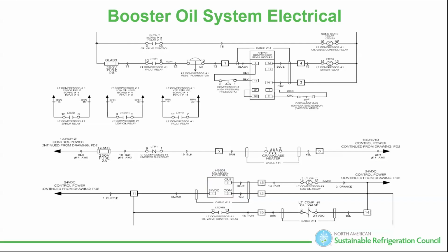Here's a great one. Here's a booster oil system using HB sensors. If you walked in and that's all you saw, could you fix it? Could you walk through the circuit? Where would you start? A lot of times that's the question. Where would you start? Well, if I had this compressor off on oil and I knew this was my troubleshooting circuit because I understand the circuit, the first thing I'm going to do is go through the sequence of operation normal, then we're going to back up and fix it.